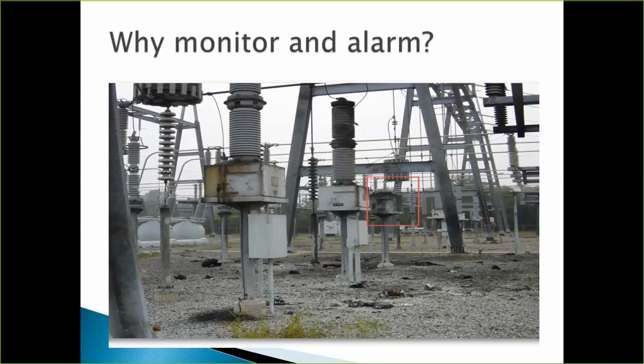So why monitor and alarm? Well, the obvious reason is we want to prevent this here. If you look in this red box, that's where a capacitive voltage transformer was. It was sitting there. I want you to pay special close attention to the debris field. This is the debris field. Look at where when it disintegrated, it shot shrapnel.